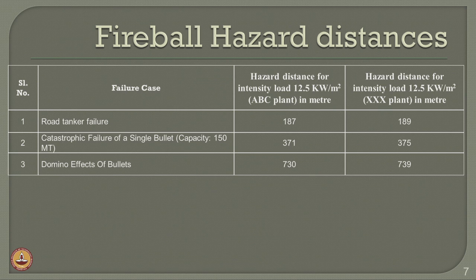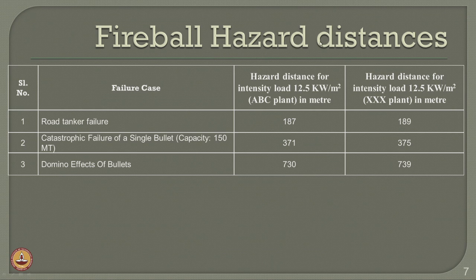Based on this, we determined fireball hazard distances for different kinds of failure — road tanker failure, catastrophic failure of a single bullet of 150 metric ton capacity, and domino effects of bullets. At a thermal intensity of 12.5 kilowatt per square meter, the domino effect generally has greater hazard distance compared to road tanker failure. The domino effect, being a cascading failure of series of bullets, has more hazard distance at both locations. However, the fireball hazard distance is not significantly influenced by the geographic location of the plant, even with different stability classes and wind velocities.